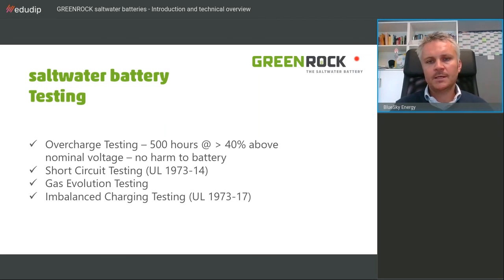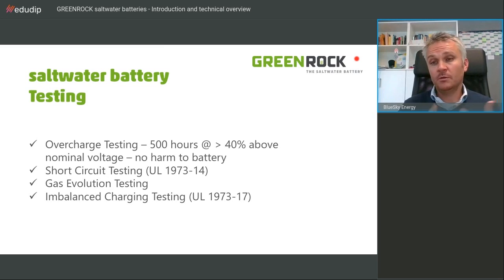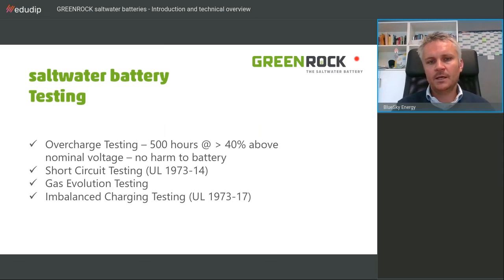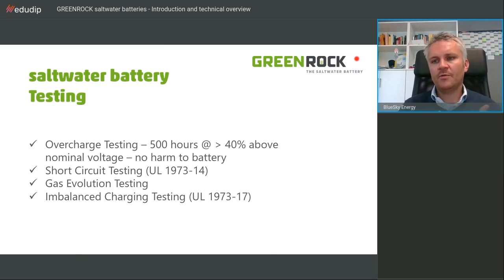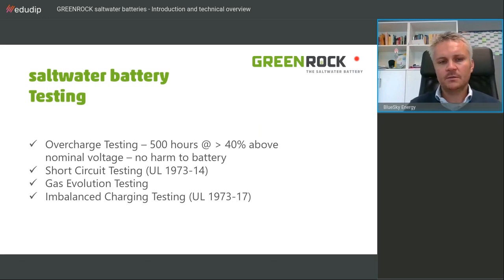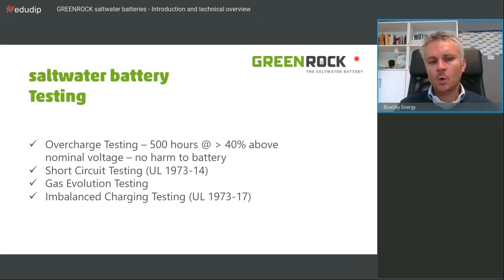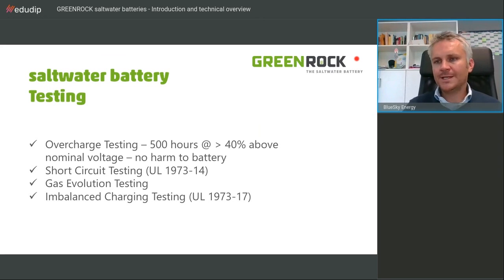Even if there would be a default on the inverter side, and the battery would be charged for 500 hours above nominal. Of course, we also did the short circuit testing according to UL 1973-14 standards, which we passed. No risk or hazardous topic came out of it. We did a gas evolution testing, which we also passed.